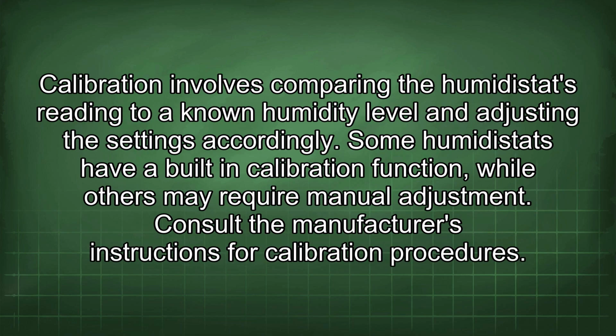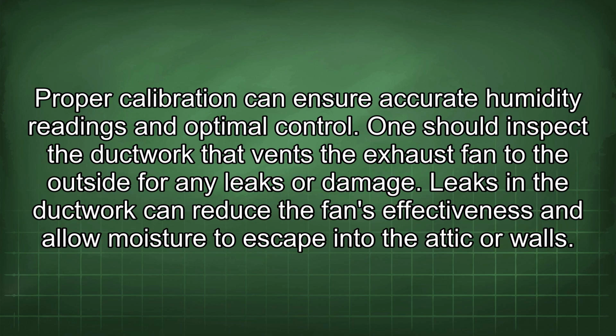To ensure the humidistat is functioning properly, calibrate it regularly. Calibration involves comparing the humidistat's reading to a known humidity level and adjusting the settings accordingly. Some humidistats have a built-in calibration function, while others may require manual adjustment. Consult the manufacturer's instructions for calibration procedures. Proper calibration can ensure accurate humidity readings and optimal control.